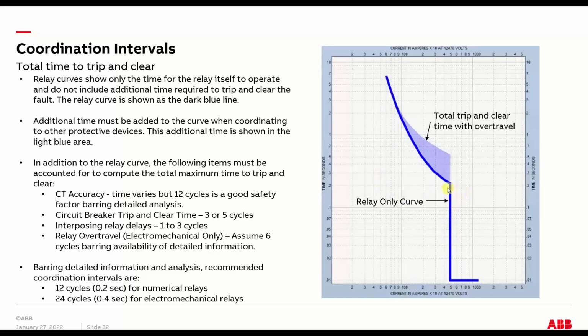So this blue line is the relay. And then I drew in this light blue hatched area, which would be the additional time that you need to be wary of to allow for the breaker to pick up, trip, and clear. And that ranges. This also includes some of the accuracy of the CT plus artifacts of the relay itself, like electromechanicals had an overtravel where they sort of spin down.